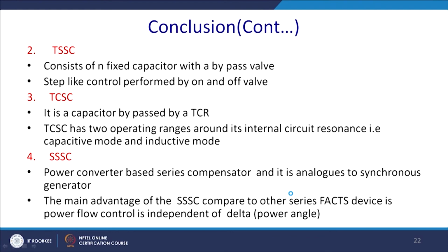In the same way, we have another FACTS device in series compensation, that is TSSC, which consists of fixed capacitors with bypass valves and steps, and it will have a step-like control. And TCSC is a capacitor bypassed by a TCR. TCSC has 2 operating ranges around the internal circuit resonance, in a capacitive mode as well as an inductive mode. Generally both operate simultaneously, but of course the preferred series device is SSSC.